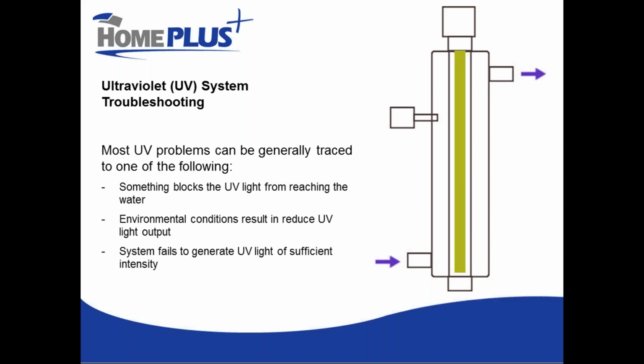So that's a very important and very common cause of UV problems. We can sometimes have environmental conditions that reduce UV light output. So a lot of UV systems allow for convection of air across the UV lamp. In between the lamp and the sleeve, there's that space of air, and they'll allow air to convect through that space for cooling purposes. But what happens if the ambient air temperature is like 3 degrees Celsius and we're drawing really cold air in? That can actually cause our UV light output to drop.